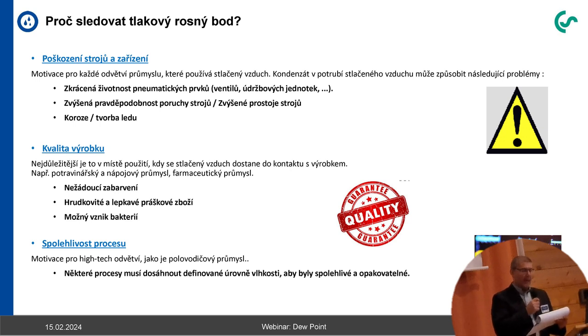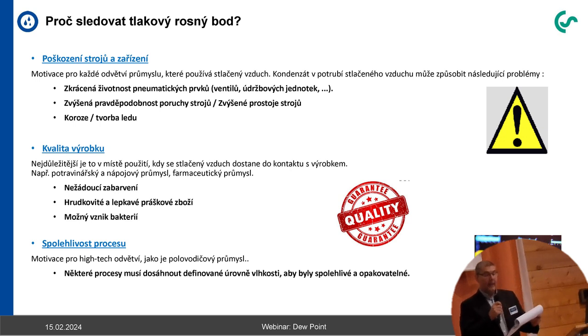So, why monitor the pressure dew point? Monitoring the pressure dew point helps you to avoid damage to your machines and equipment. Nearly every industry needs compressed air, and if you have condensate in your compressed air, you will have a lot of problems. You will have a reduced lifespan of your pneumatic elements and valves, increased failure of your machines, and corrosion inside the pipes, and of course it also affects your product quality.